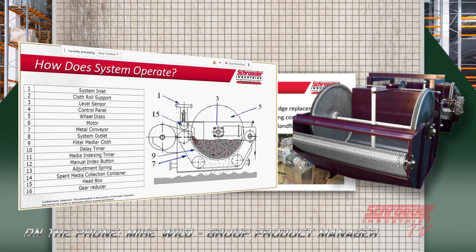Looking at the system, the operation is very simple. On the left side, next to number 15 below that is where the roll of media would go. It's fed through the system by a conveyor belt on the bottom. Number five, the wheel disc, has a rubber edge to it — this compresses the media against the conveyor and increments it along. Water is fed from the top or from the side, comes into a header box which slows down the velocity of the water and distributes it across the length of the media.